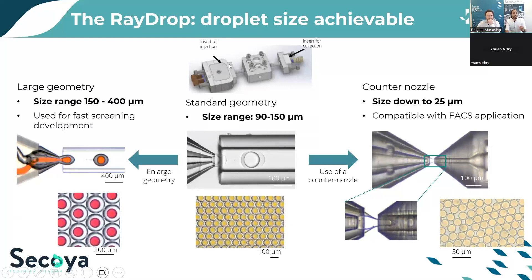Practically, the RayDrop is composed of three main elements: an insert with the injection nozzle — which can be removed and changed, for example from single emulsion to double emulsion nozzle — the body which contains the chamber, and the outlet collection capillary. The standard double emulsion geometry generates droplets from approximately 90 to 150 micrometers. To generate larger double emulsions, you simply change the double emulsion nozzle and collection capillary to bigger sizes, enabling double emulsions from 150 up to 400 micrometers.